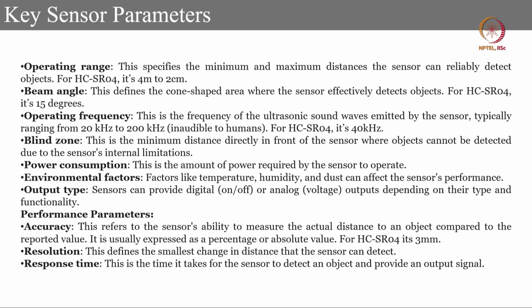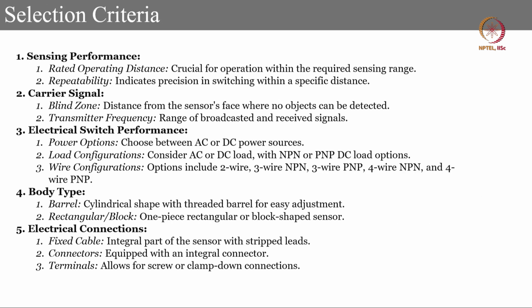The performance parameters are accuracy, resolution, response time. Accuracy refers to the sensor's ability to measure the actual distance to an object. Resolution is defined as the smallest change in distance that the sensor can detect. And finally, the response time is the time it takes for the sensor to detect an object and provide an output signal. There are selection criteria that we also need to consider.